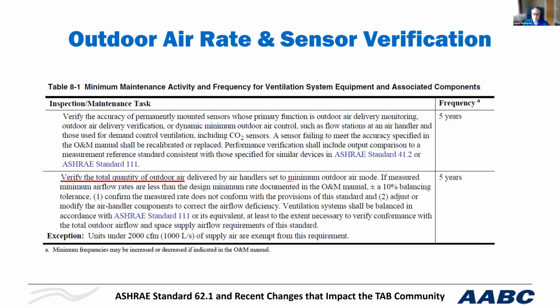There's another thing here talking about verifying outdoor air. Well, of course, this is the most important thing. It's the foundation to make sure that we have good indoor air quality and ensure that we have the right ventilation coming into the building. So why would the outdoor air fail? Well, you have degradation of the mechanical components. You have actuators that can break or slip. You have linkages that can break as well.